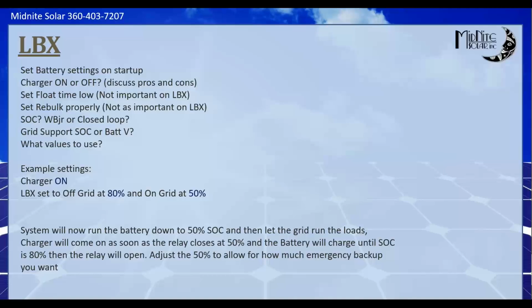Here are some things you'd do in this mode, and you'll see they differ a bit. Float time being set low isn't really important in LBX because LBX takes priority over the battery charger. We discussed the pros and cons of the charger off and on. Personally, I'd program the Rosie up for all the proper charging setup you want, then turn just the charger off, so if I wasn't the end user but the installer, I could leave a quick sheet for the end user that says press this, do this, enable the charger, and now if a storm's coming you'll have a full battery. It'd be quick to explain. Rebulk also isn't as important because as soon as it closes the relay, it would actually charge if you had the charger enabled.